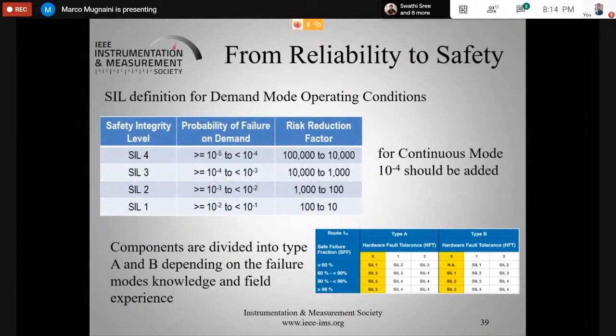Actually there are five. SIL 0 means you don't need any kind of safety prescription. SIL 1 means you have to bring your system to have a probability of failure on demand between 10 to the minus 2 and 10 to the minus 1. If you want to raise your system up to safety integrity level 4, the probability of failure on demand should be lowered from 10 to the minus 5 to 10 to the minus 4. The higher the safety integrity level required by your application, the higher the effort you have to bring in order to build your electronics or hardware in general.